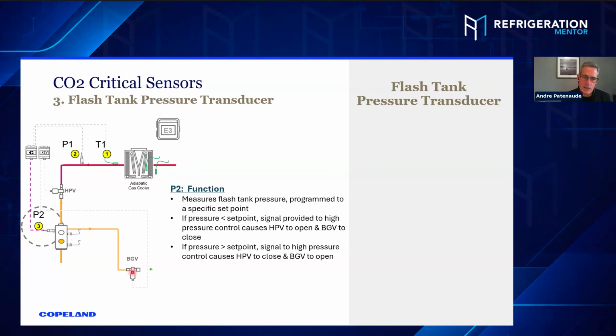And so really that flash tank is a simple static set point, like I said. And this bypass gas valve is nothing more than an EPR. It works just like an EPR. If you understand how an EPR works at the outlet of a case, anything below that set point, the valve will close to make sure it builds up. It doesn't fall below its set point, to keep that temperature from going lower and freezing product. But anything above that, the valve's open. And this does a similar thing. If the flash tank pressure is higher than its set point, okay, I'm going to open, I'm going to relieve the pressure in that tank. But if it's lower, I need to close to build the pressure in the tank. So that's all it's doing.